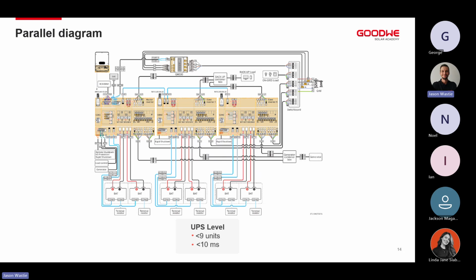So that is the parallel solution, or how we do parallel on the inverters on the ETLV series. In the user manual, you'll see there's quite a nice diagram that shows you exactly how everything should be wired, as well as how to connect the smart meter, energy meter that needs to be purchased as well. One thing to note with the system, the additional purchase that is required for the ETLV series in paralleling is the GM330 energy meter, as well as the 3 CTs that need to be installed with it.